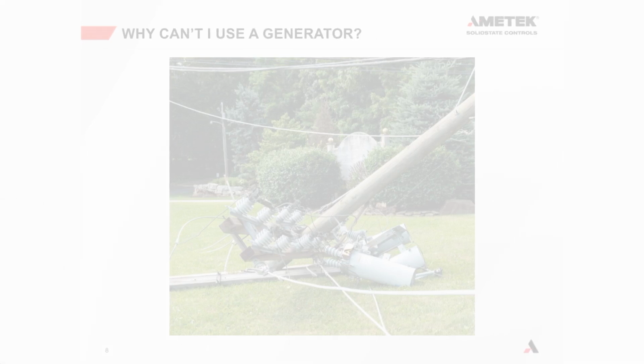And the problem with that is whenever we have a power loss, and you can see in the picture here, that can be whether a power pole goes down from a weather event or whether it's physical damage to the power pole, like a car crashes into it, or whether there's a fire at the substation in the transformer. Whatever the reason is, we do not know when the grid is going to lose power. It's very, very rare that we know the exact time that the grid is going to lose power. So there's no way we can preempt the starting of a generator to cover any power issues that we're going to have. It's retroactive. The power outage has to happen. We then have to sense that power outage, and then we have to start the generator and get it up to speed.